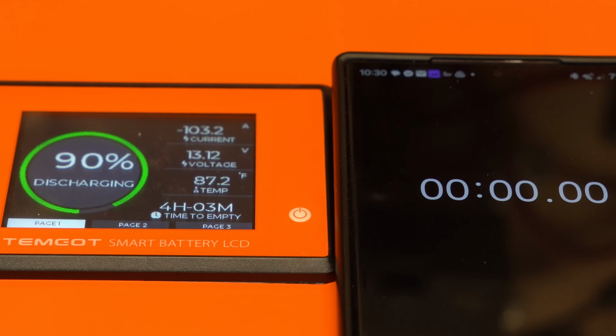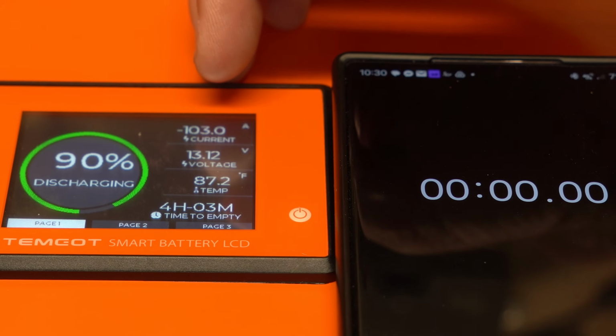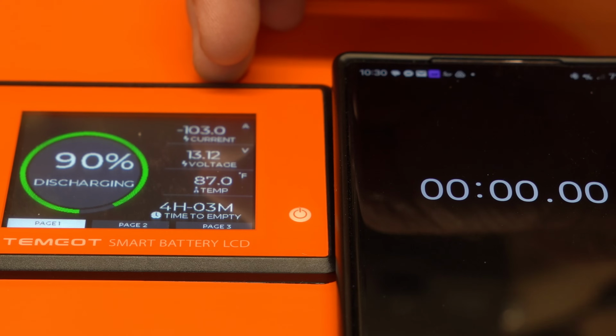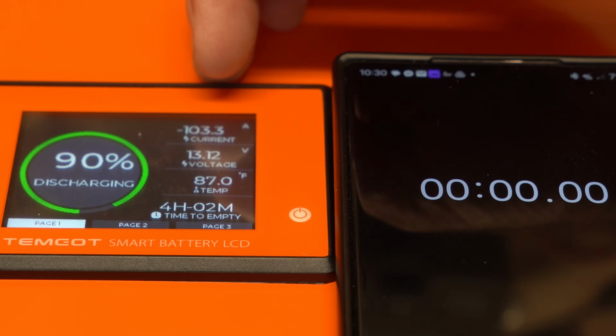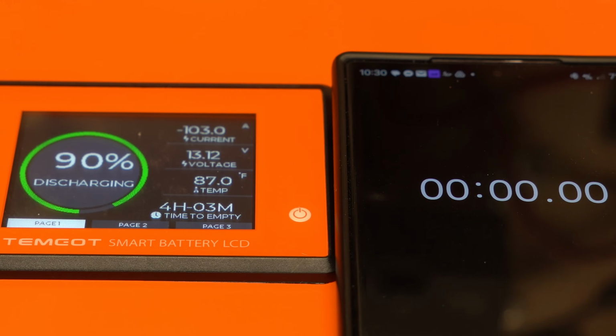All right, let's do some load testing on this battery. It's rated for a max discharge current of 250 amps. You can see I am currently pulling 103 amps. I have two separate 2,000 watt AC inverters connected right now. Let me add some additional load from the second AC inverter. I'm sure we're going to get some fan noise from this, and this should spike us up.